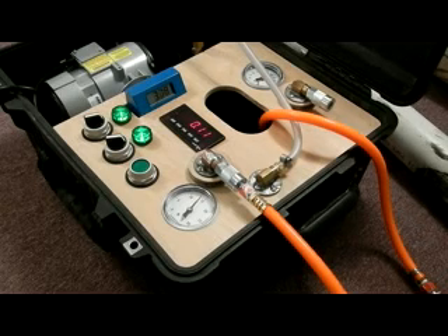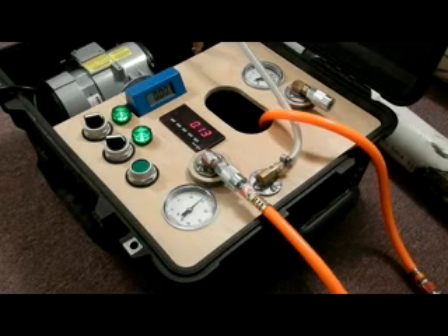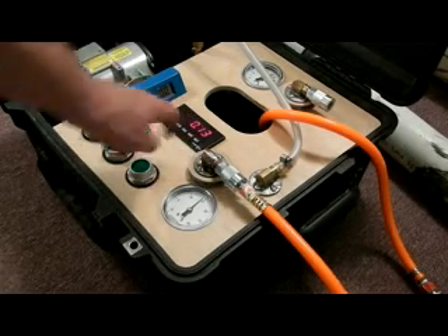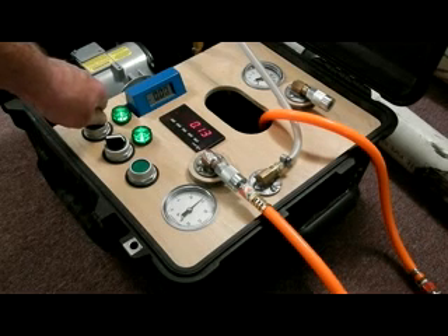As we approach 0 on the flow meter is when we've reached our correct volume. As we approach 0, anything under about 0.5 liters per minute. Here we're at 0.07 and 0.13, which is the theoretical volume. We now shut off the manifold and the void, and we can shut off the compressor. And our meter is reading 0 flow and 0.13 cubic feet, which is the theoretical volume of the cylinder.